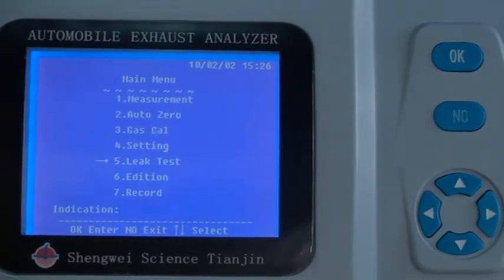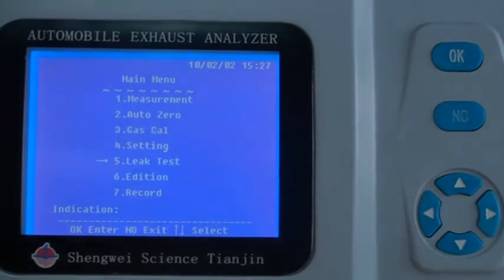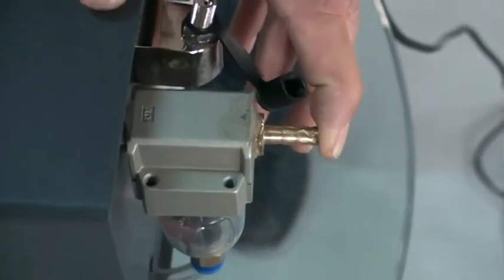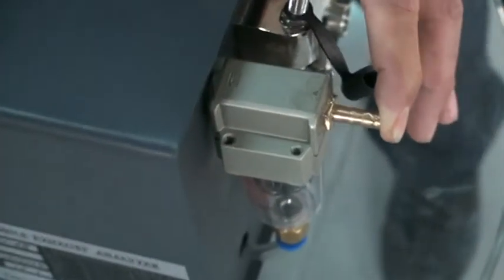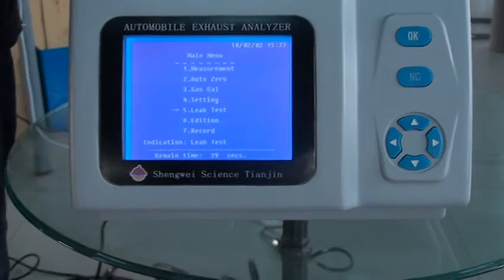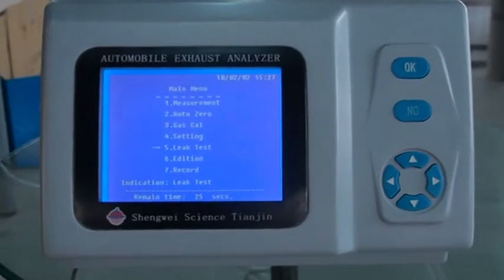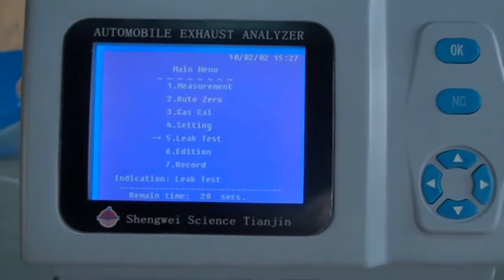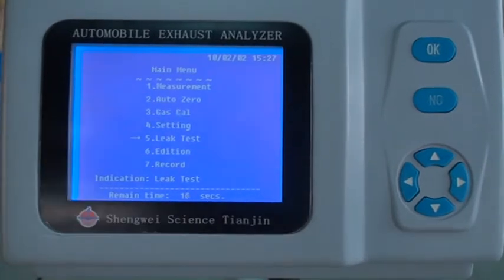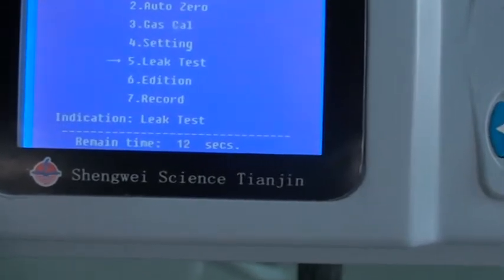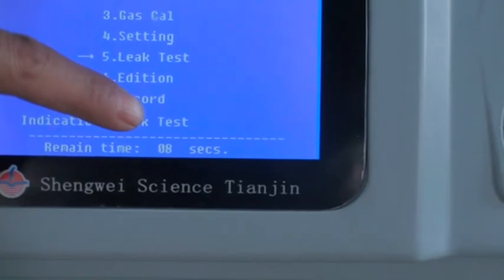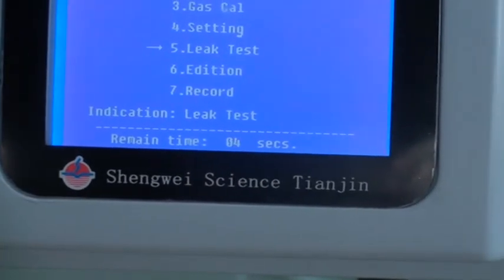Then plug the sampling tube and press OK. The pump starts. When it shows 20 seconds, stop, and take the plug off the winch. At the end it will indicate whether the leak test passed or failed. If the internal tube leaks, the leak test fails.